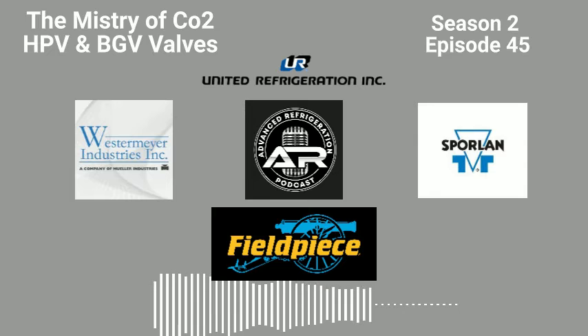So inside of whatever controller is controlling it is a COP chart. So COP charts exist for every refrigerant out there, for compressors, for everything. It's a coefficient of performance chart. So the problem with CO2 is above 87 degrees, that chart is no longer a good reference, because it doesn't share that pressure temperature relationship. So what these manufacturers have come up with, Danfoss, Emerson, Carel, RDM, Micro Thermo, they've all been fighting this fight, and they all think they have the COP chart where they think it maps out, where they think it may share a pressure temperature relationship. They can't really tell, but they have this chart with their pre-programmed algorithms in there where they think it is. Everybody's a little bit different. I'm pretty sure most of them are probably the same, and half of them probably stole the algorithm from each other.